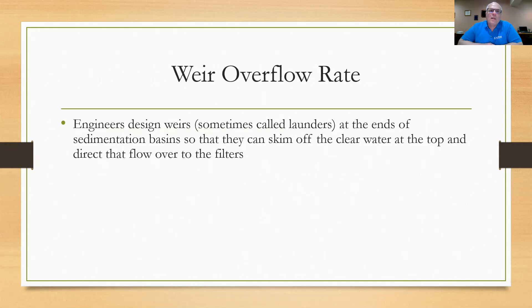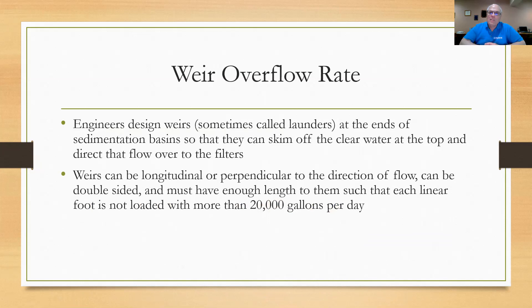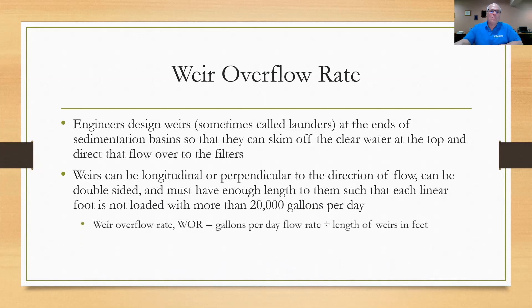Let's move on to weir overflow rate. Engineers sometimes call weirs 'launders' when they're installed in your basins. The launders at the ends of sedimentation basins skim off the clear water at the top and bring it over to the filters — typically the top inch or two of water. Weirs can be longitudinal or perpendicular to the direction of flow and can be double-sided, but they must have enough length so that each linear foot of launder is not loaded with more than 20,000 gallons per day. So the weir overflow rate (WOR) is simply the gallons-per-day flow rate divided by the length of weirs in feet.